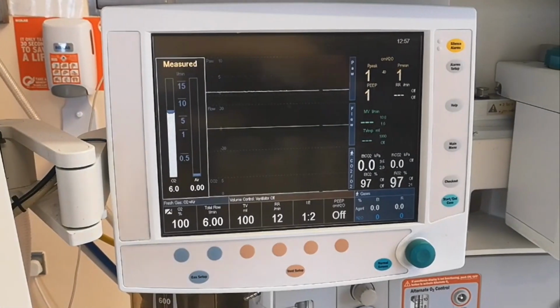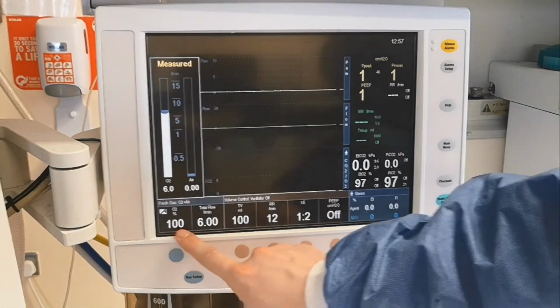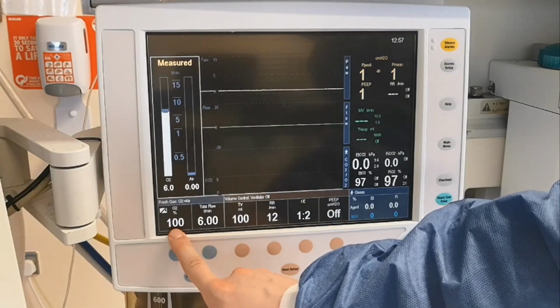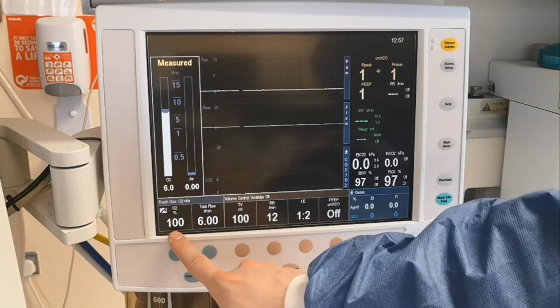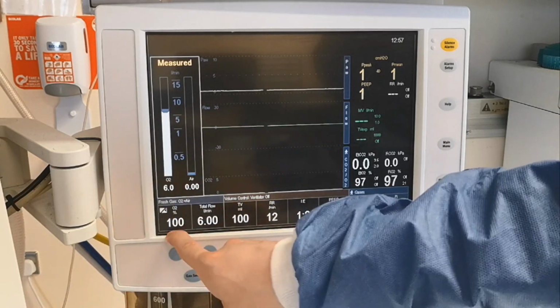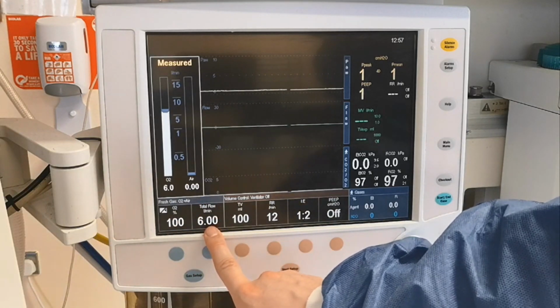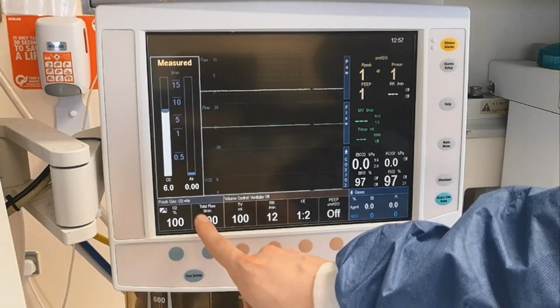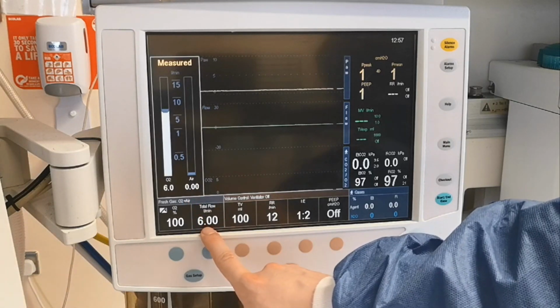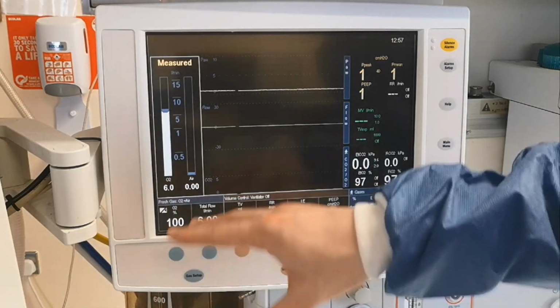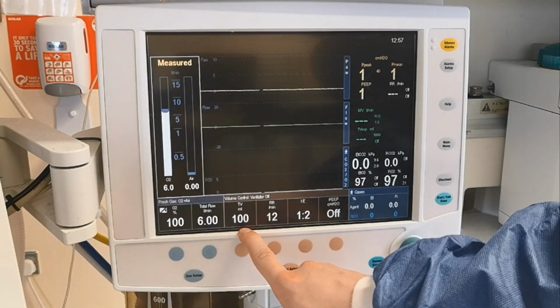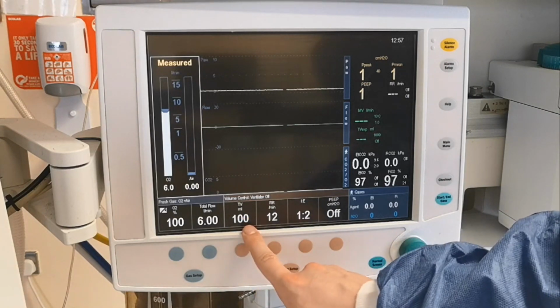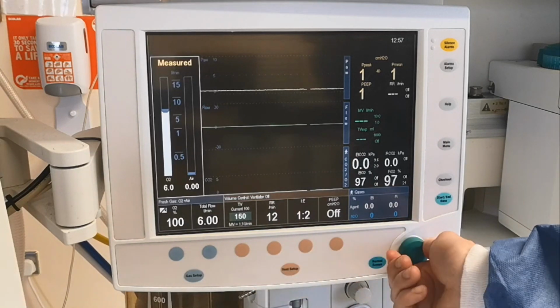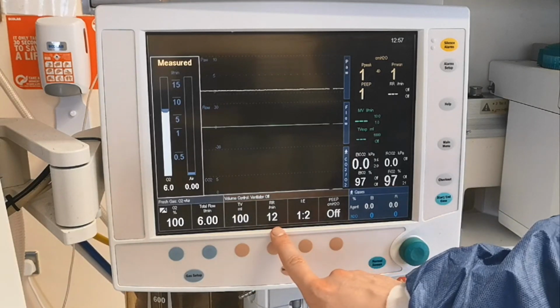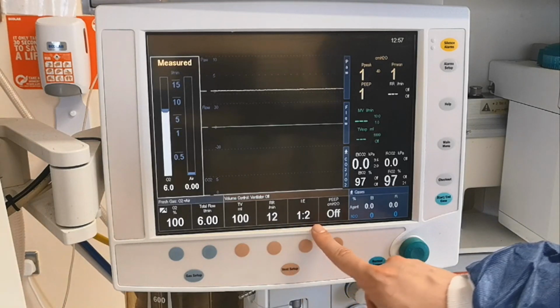It could look a little intimidating here, but let's explain the little numbers. This is oxygen, the concentration of oxygen that you give. This is the total flow. That means that 6 liters per minute is the volume of fresh gas that's coming from the wall and gets added to the circuit every minute. This is the tidal volume, which comes preset at 100 milliliters, so you're going to have to change that if you're ventilating an adult, of course. This is the respiratory rate, the inspiration to expiration ratio, and the PEEP.